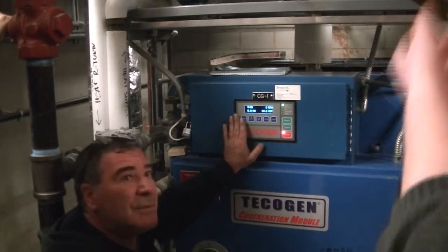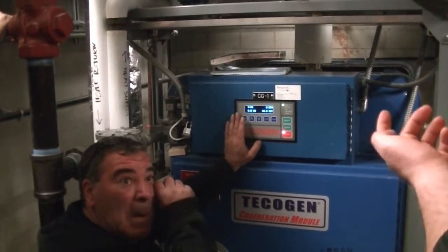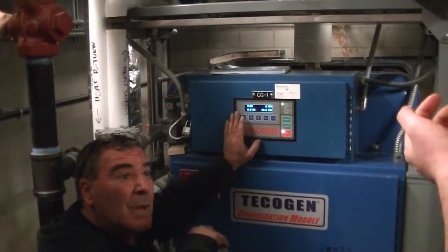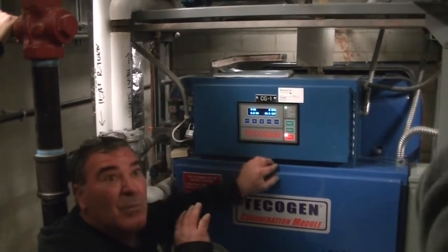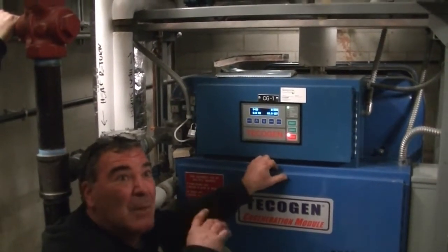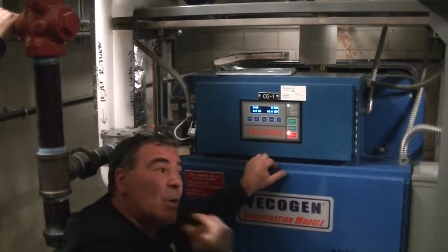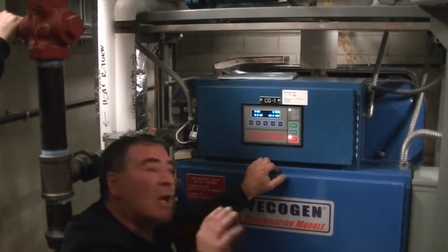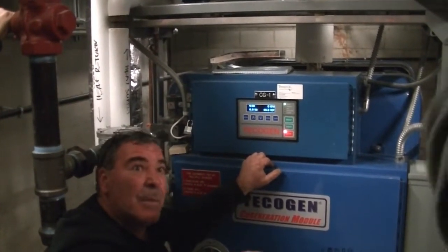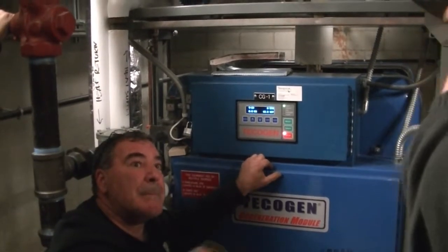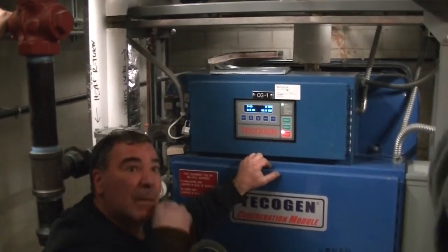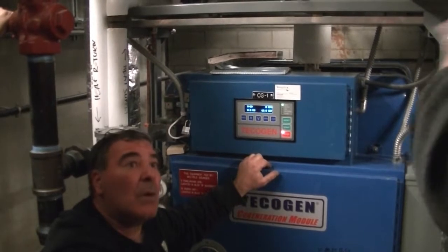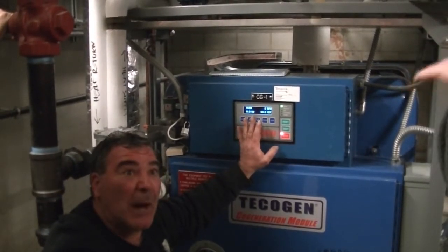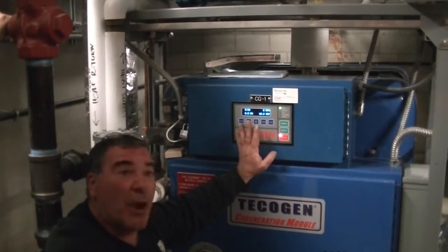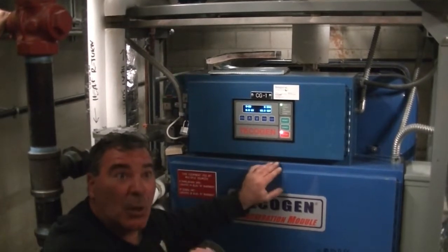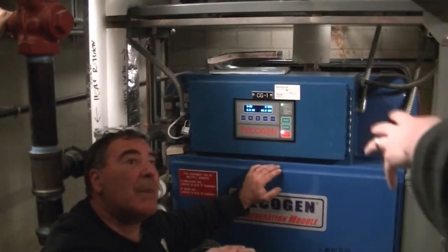So the alarm light goes on when it's in low temperature fault? It goes in alarm for a lot of things. You have an oil level alarm, oil temperature alarm. There's also a thing called pre-alarms. But when this thing is generating too much heat and it shuts off, is that also an alarm? Yeah, it says low thermal power, meaning there's no load. So that's normal operation.